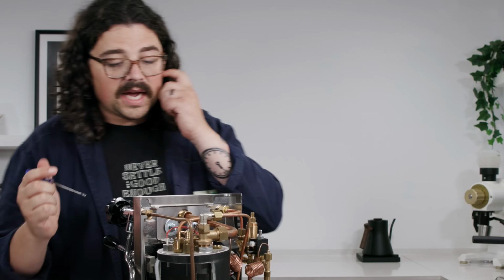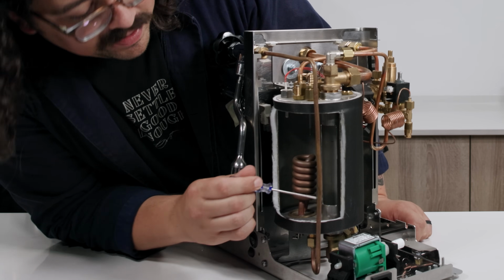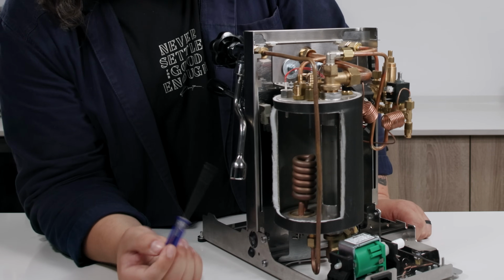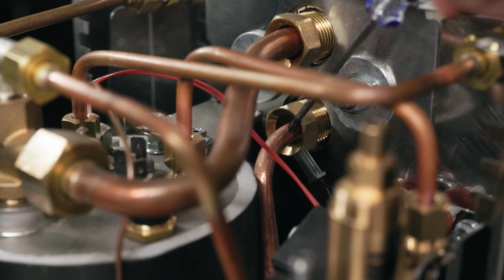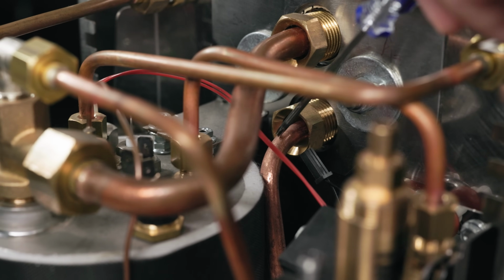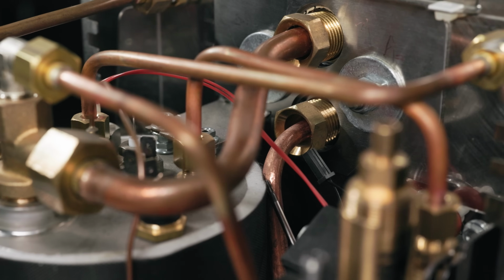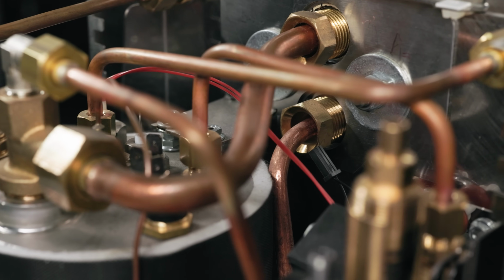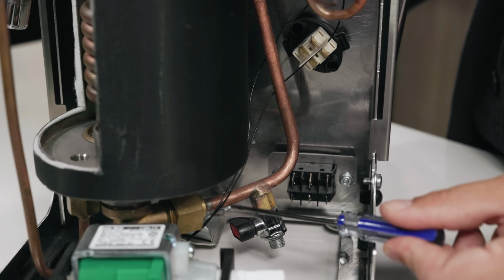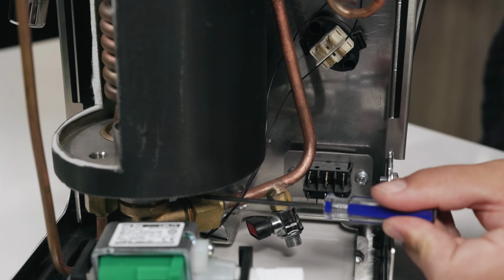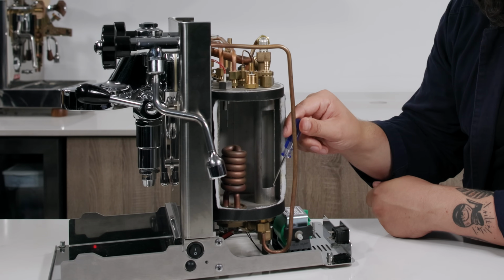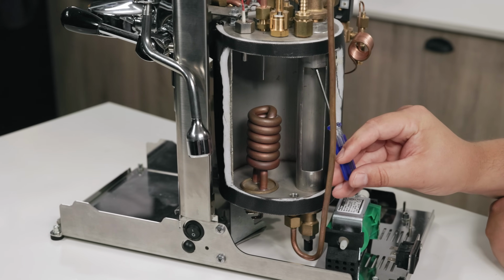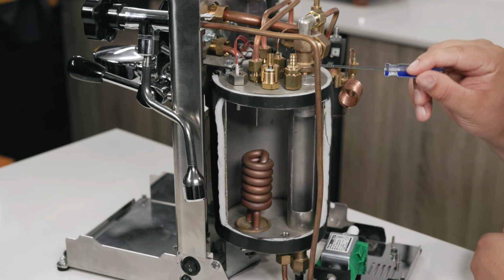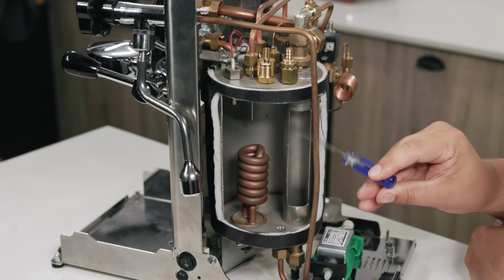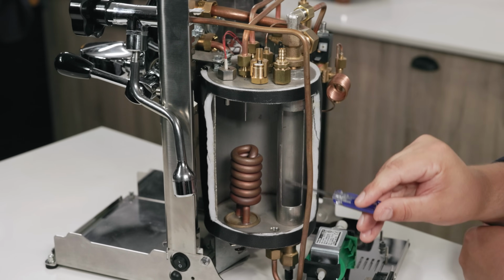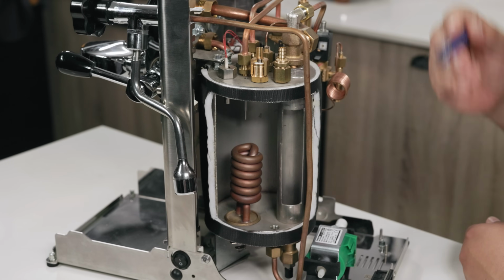All right, so let's get inside the boiler itself. So in here, you have an inlet down below, which is from the thermosiphoning. The outlet of the group head, so it's the bottom part of the thermosyphon. So it says hot water, and it comes down this way beside the boiler. It keeps coming down and around, and it feeds back into the boiler right here. We have the inlet down here of the hot water, and then we have cool water that comes from above from this inlet valve. So we have hot water and then cool water. So this keeps in flux with fresh water and with recirculated hot water.